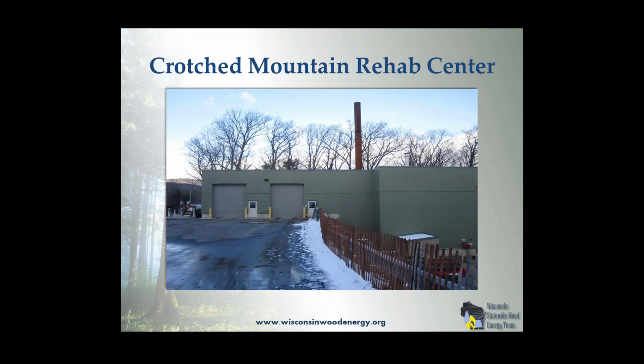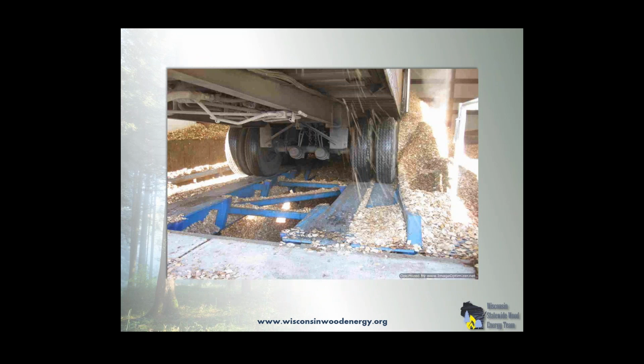Crotched Mountain Rehab Center, this is one of the more creative spaces that they made use of for fuel storage. Those two doors, you can look at the space. It's about 30 feet deep by approximately 30 feet wide, 30 by 30 more or less. And in order to get fuel to the back and make use of the space, the height that they had, they put this track system or bridge system up over top of the storage.